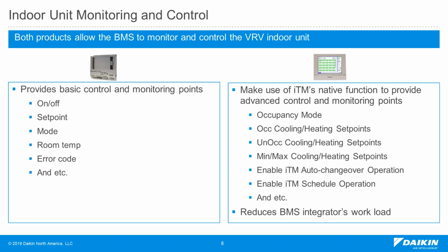So both products enable the BMS to control the VRV system by controlling the VRV indoor units. In a VRV system, the outdoor units are not controlled directly by the BMS, but the outdoor unit operates automatically based on the indoor unit's demand. So the BMS only needs to control the indoor units, and both of these two products provide the BMS this capability to control the indoor unit points. But the difference between these products is that they provide different control and monitoring points even for the same indoor unit. The BACnet gateway provides just basic control and monitoring points, such as on/off, set point, mode, and monitoring room temperature and error code. But the ITM gateway, on the other hand, can make use of ITM's native functions and provide more advanced points.